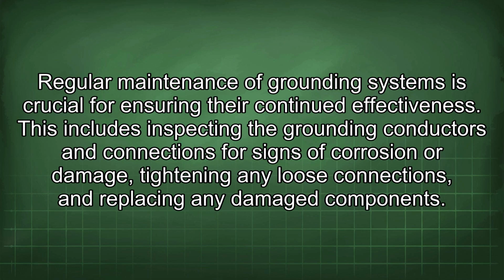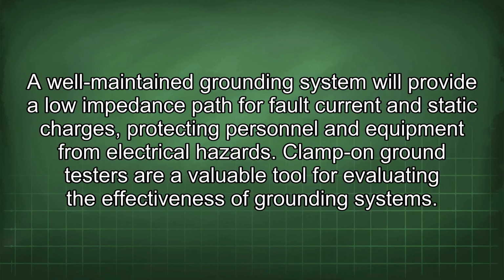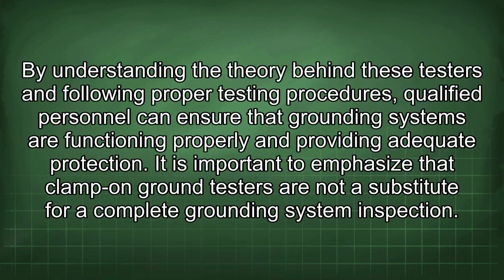Regular maintenance of grounding systems is crucial for ensuring their continued effectiveness. This includes inspecting the grounding conductors and connections for signs of corrosion or damage, tightening any loose connections, and replacing any damaged components. A well-maintained grounding system will provide a low impedance path for fault current and static charges, protecting personnel and equipment from electrical hazards. Clamp-on ground testers are a valuable tool for evaluating the effectiveness of grounding systems. By understanding the theory behind these testers and following proper testing procedures, qualified personnel can ensure that grounding systems are functioning properly and providing adequate protection.